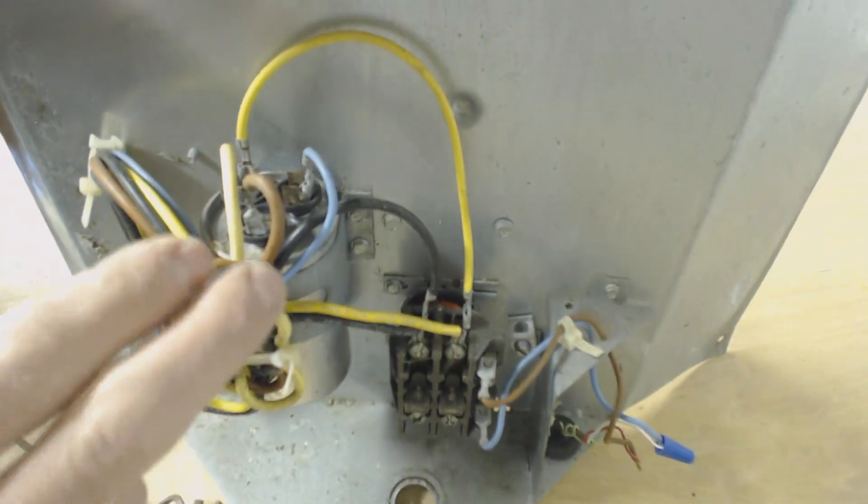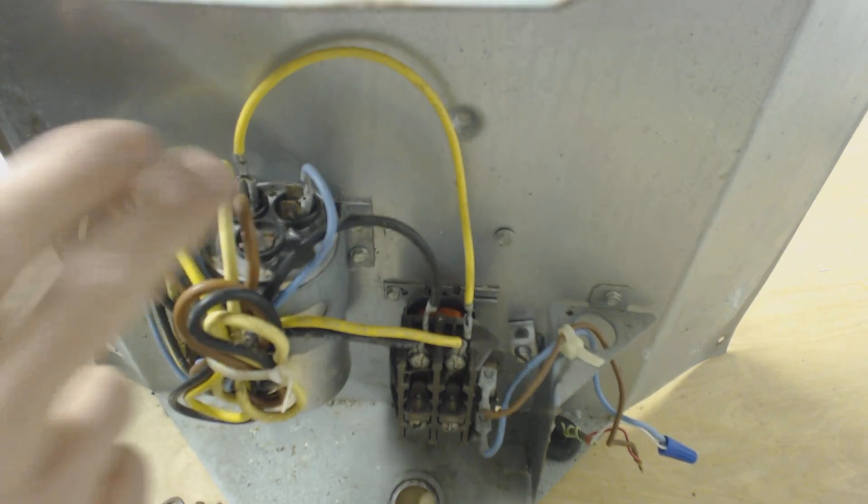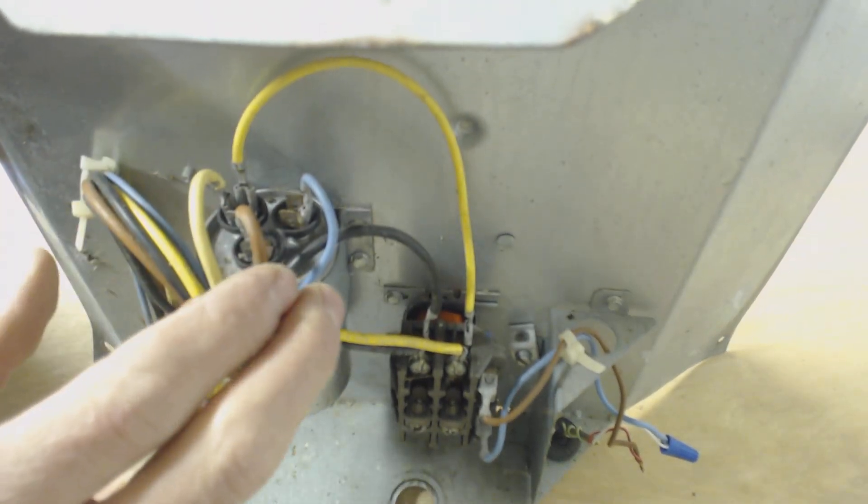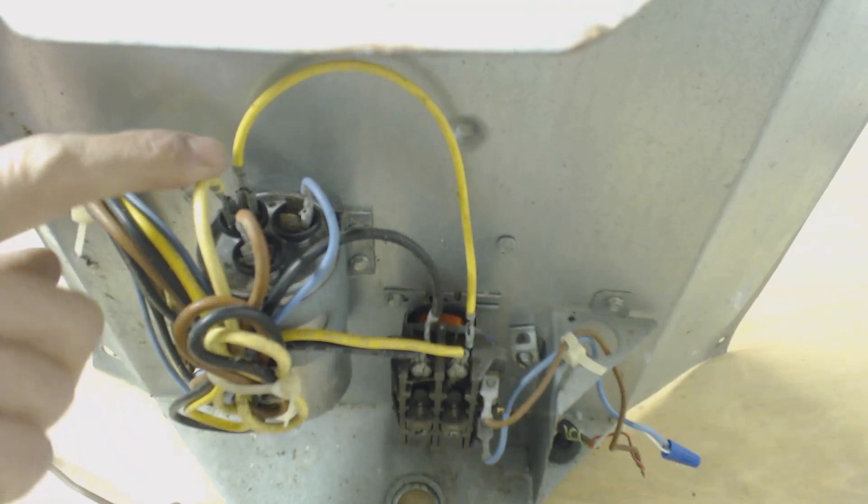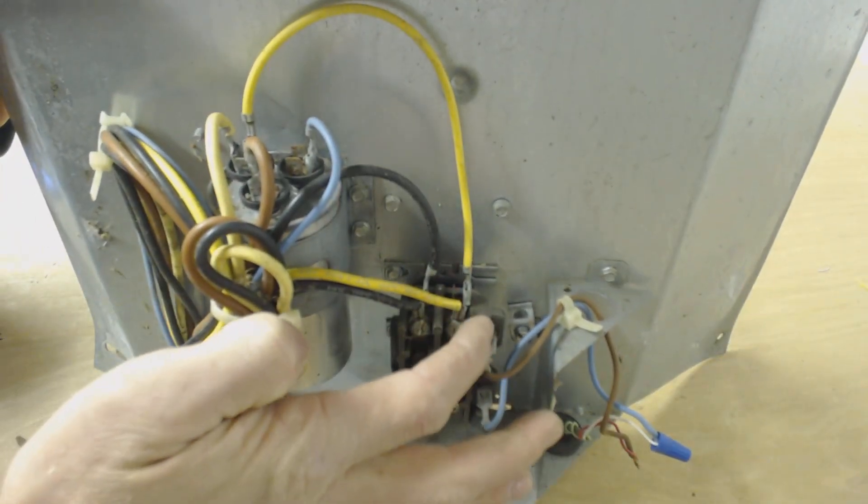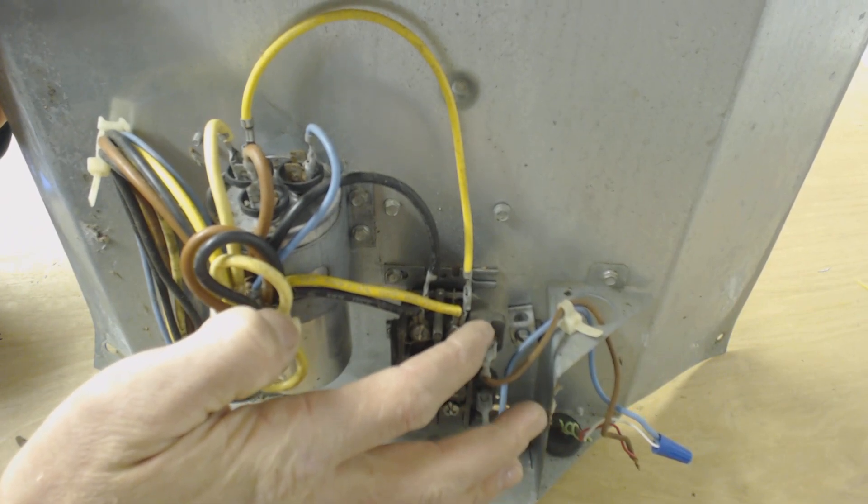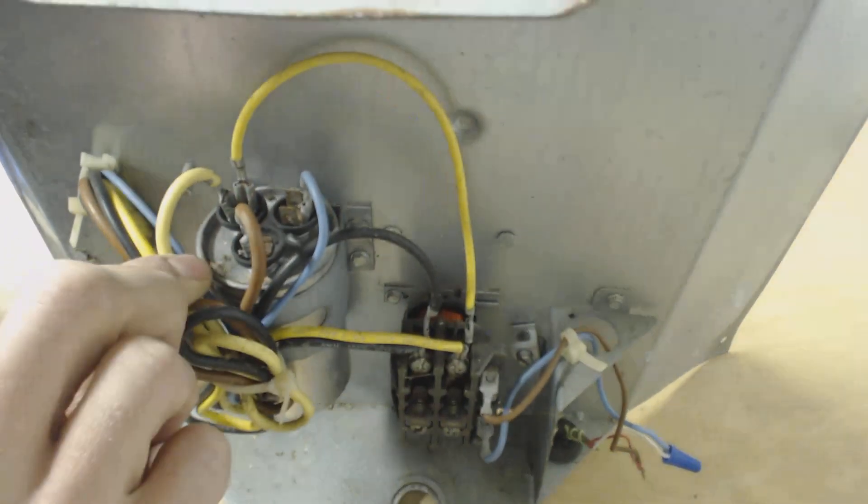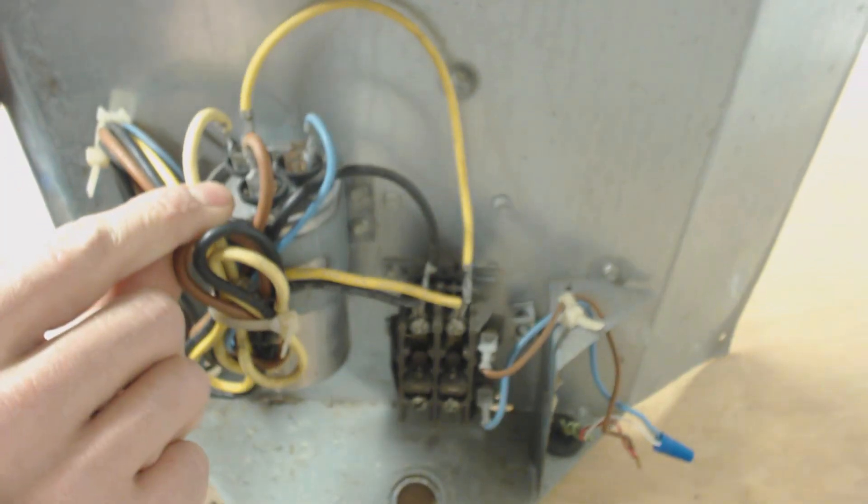So you have your capacitor up here. You have the yellow, where the yellow wire is attached into it, right here. That usually gets powered directly off of the contactor. And then you look at the capacitor where it says C or Herm.